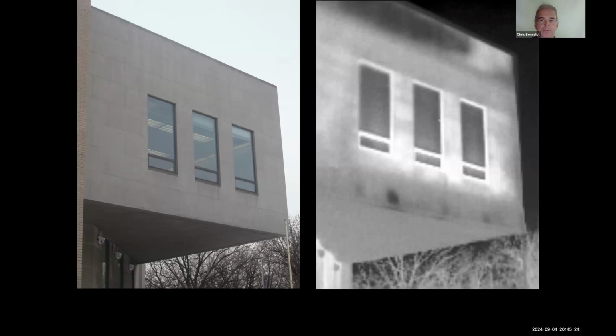So that brings up the question, why is the parapet warm at the right? That's because warm air from inside the building is leaking out there. You notice it's hotter than the wall below it. So there's some direct connection, like where the roof ceiling structure meets the wall structure, there's an air leak, and air from in the building is being pushed out there.